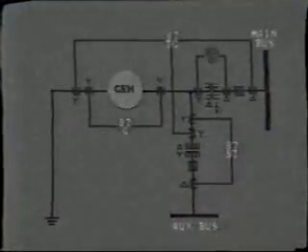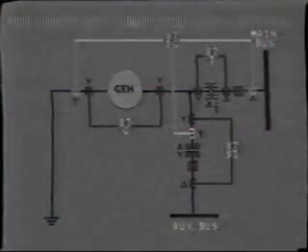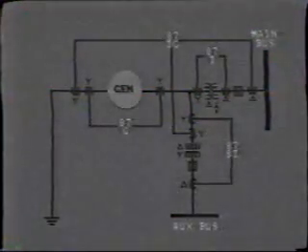Normally, differential protection is installed across the transformer, 87T in this case. The same thing goes for the unit service transformer. Here once again, separate differential protection, 87ST, is connected across this transformer. It is also quite common to add further differential protection by linking CTs across all three items of equipment. That is, the generator, the unit transformer, and the unit service transformer. We can call this 87TG. Operation of any one of these differential circuits will trip the main breaker and associated equipment.